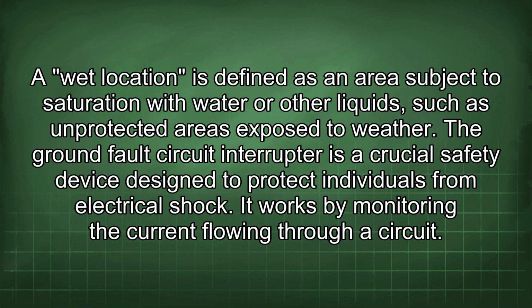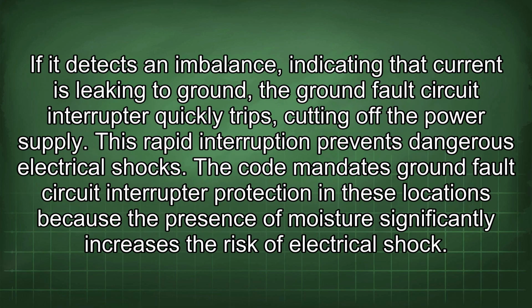A wet location is defined as an area subject to saturation with water or other liquids, such as unprotected areas exposed to weather. The ground fault circuit interrupter is a crucial safety device designed to protect individuals from electrical shock. It works by monitoring the current flowing through a circuit. If it detects an imbalance, indicating that current is leaking to ground, the ground fault circuit interrupter quickly trips, cutting off the power supply. This rapid interruption prevents dangerous electrical shocks.